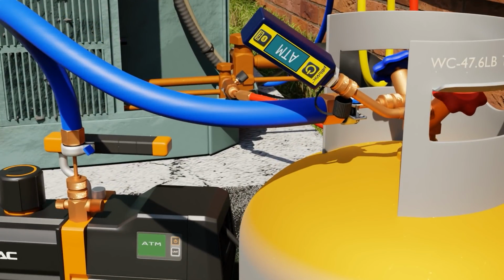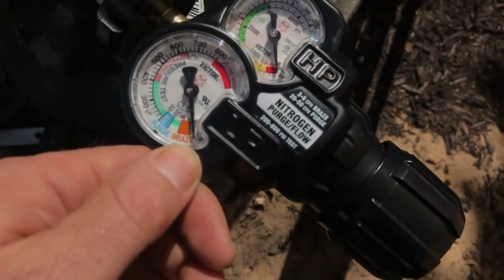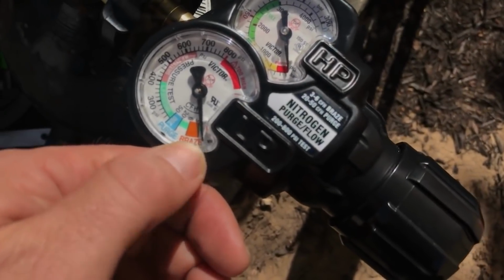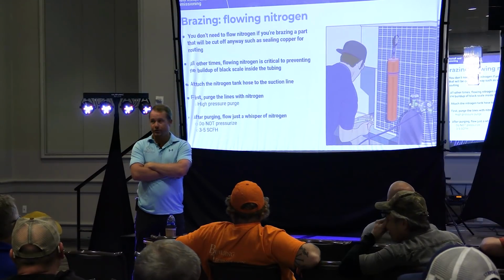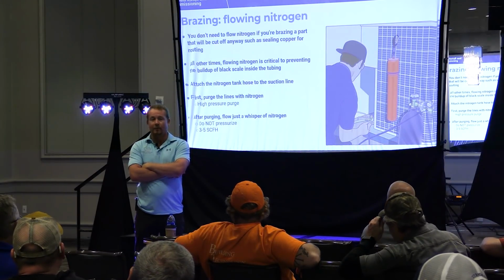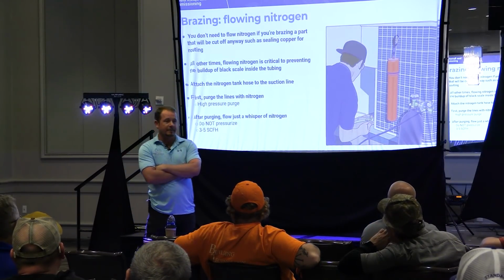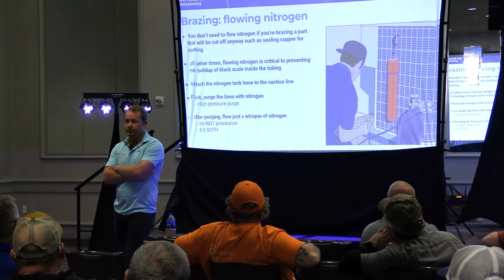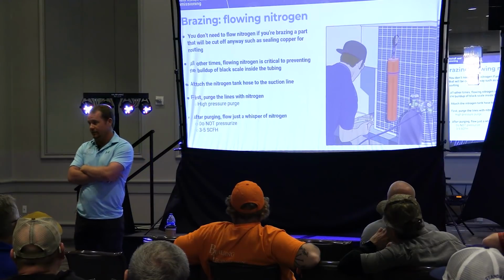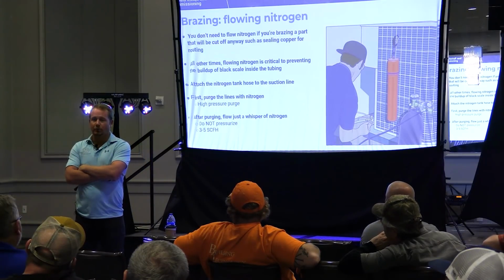Now, pulling a vacuum and flowing nitrogen will save you repairs. It will make TXVs plug less. It will make filter dryers plug less. It will save compressor issues. So just do it, and it isn't hard at all. Here's what I want to say about this, because a lot of times the excuse that technicians and installers use, there's two excuses they use for not flowing nitrogen. Three. One is, I've tried it and it just keeps blowing the last joint out.